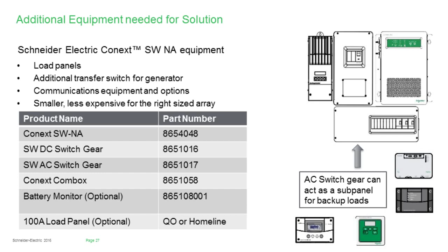To complete the webinar, we're going to be talking about exactly what happens when we have an AC coupling solution and how that PV inverter really interacts with the energy storage solution. There really are two styles of AC coupling: curtailing and non-curtailing. We'll cover the first part, which is the non-curtailing PV inverter. So in this case, we have an inverter that is IEEE 1547 compliant. And what's going to happen is, of course, when we get to 60.5 hertz, the AC source is no longer qualified and that PV inverter is going to stop producing power.